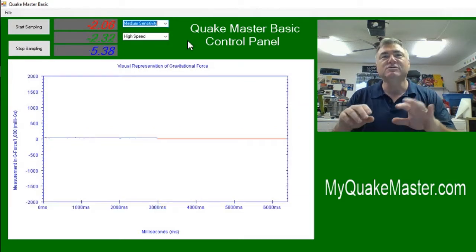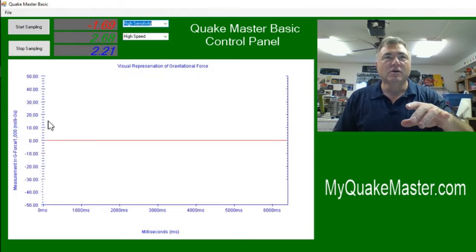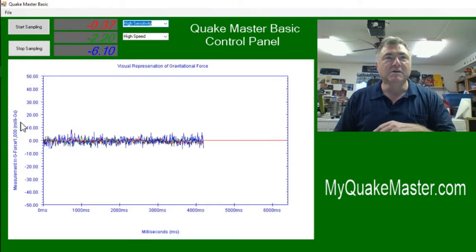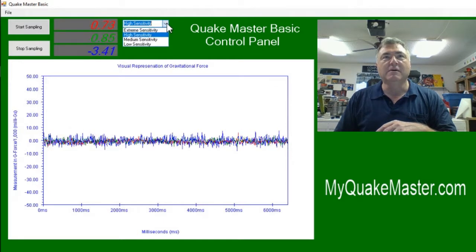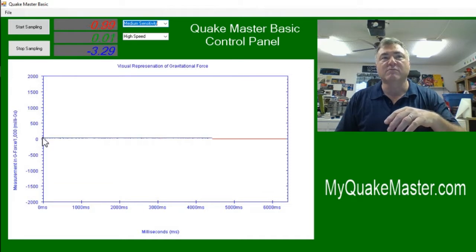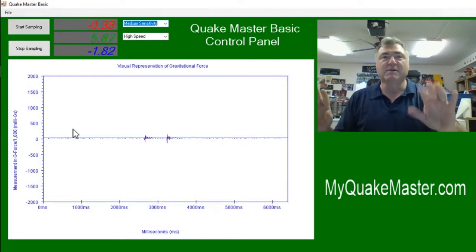Now, it doesn't look like it's doing much, because notice that in high sensitivity, we were over here in measurement in milli-g's, 10, 20, 30 milli-g's. Well, when we get to medium sensitivity, rather than 10 milli-g's, we're talking about 500 milli-g's. So all those little vibrations you just saw around the 10 milli-g range are just these little tiny things. If I tap on the desk, you'll see little tiny vibrations. So much less sensitive. But I'm going to pick it up this time. Let's see what happens.